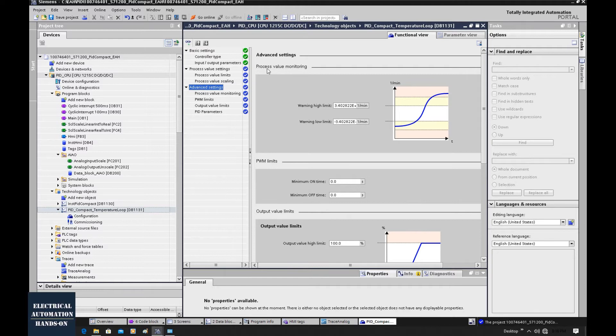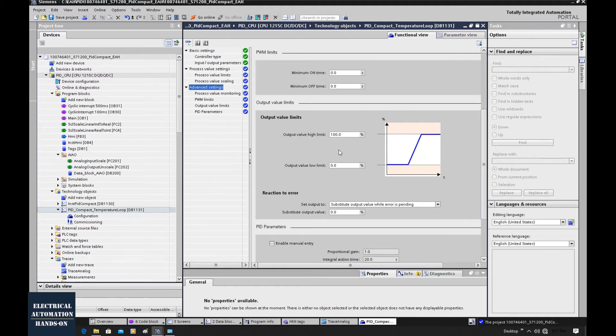Let's go to the advanced settings. Under process value monitoring, we can set thresholds — when the system goes outside this range, the PID function block gives us an alarm. For output limits, often we set 0 to 100%. But in some special cases — for example, I had a case where I was using PID to control a heater coil, and putting 100% energy would burn the coil — so I had to limit the output to less than 70%. You can set those limits here depending on your case.